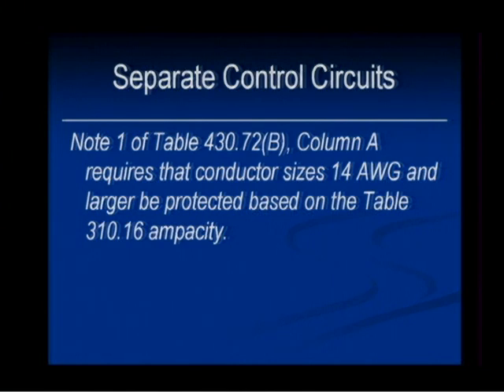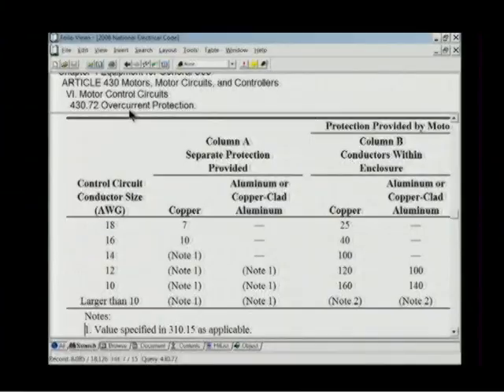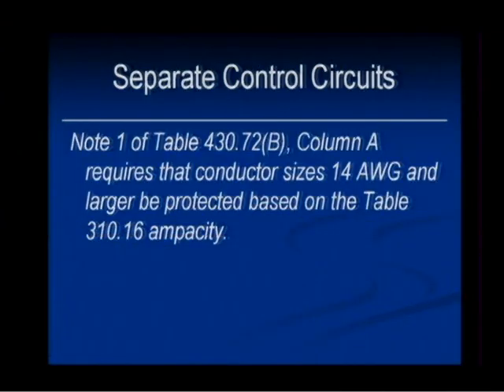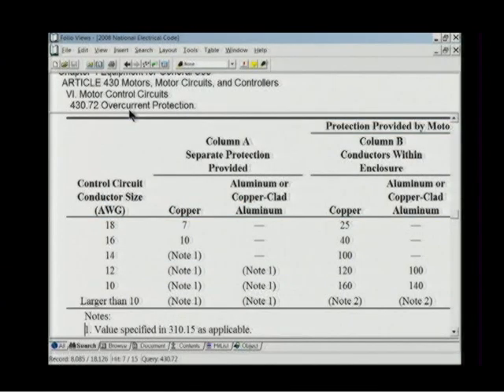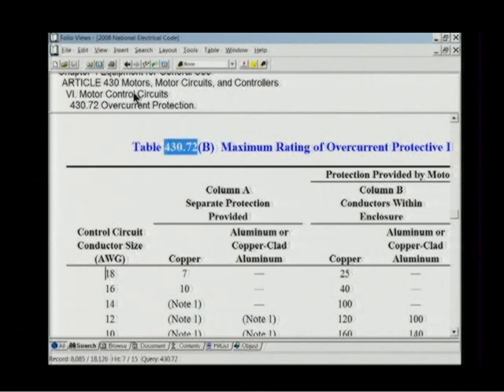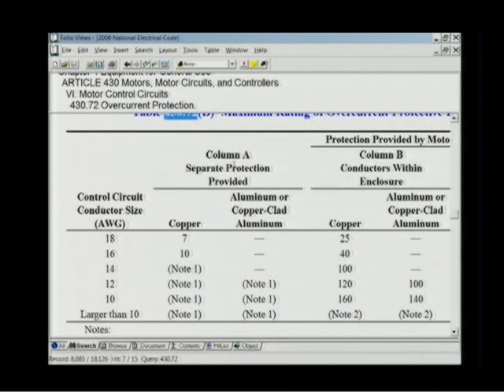Note 1 of Table 430.72(B), column A, requires conductor sizes 14 and larger be protected based upon Table 310.16. If you're an electrician or if you have electrical background, you should be familiar with Table 310.16 and how you size protection for conductors. Let's go ahead and jump to the code. That slide said what? 430.72(B), column A. We are in Article 430. Relates to motors, motor circuits, and controllers. We are going into Part 6 of Article 430, which is motor control circuits. We are in Section 430.72, overcurrent protection of motor control circuits. And we are now looking at Table 430.72(B). And there's a column A, which talks about separate protection provided.